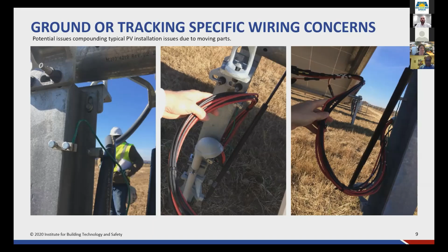One of the two most common issues that result in a thermal event or negative outcome is improper management of wires, loose connections, or improper terminations, and non-compatible connectors.